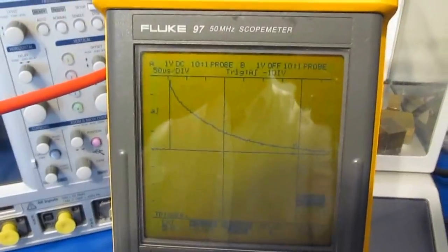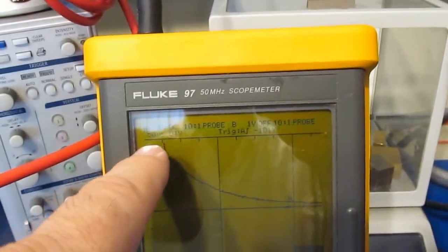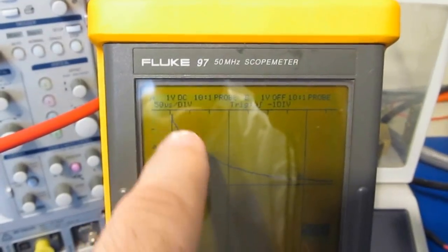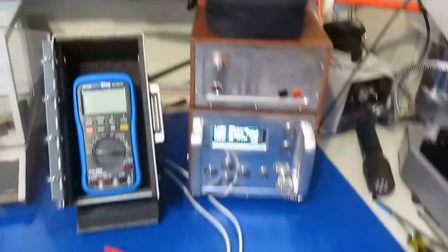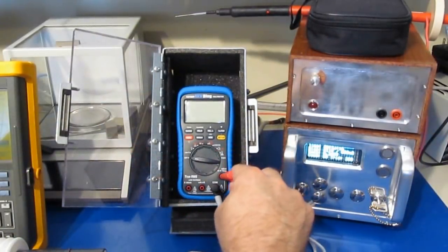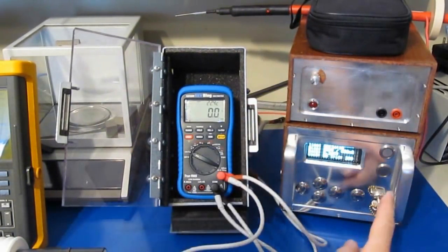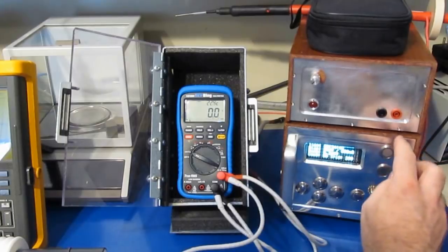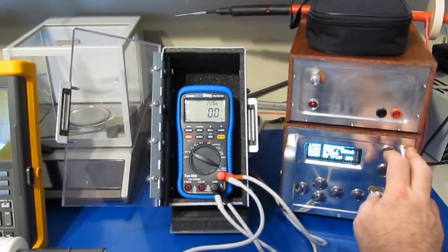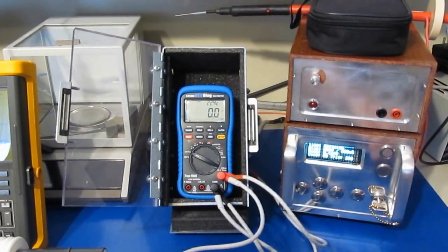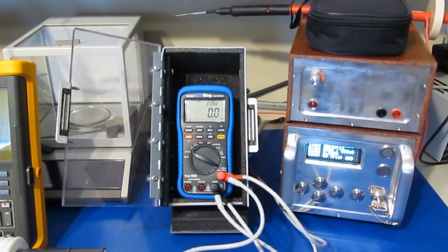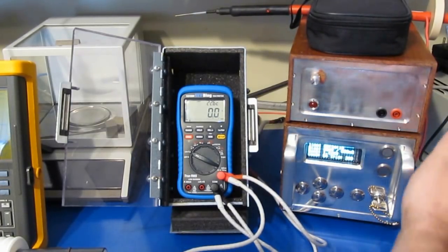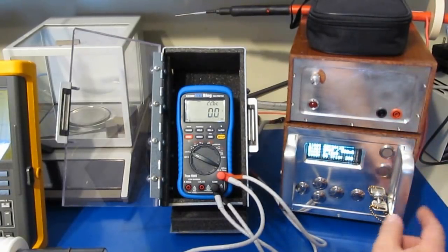Wow, the glare is just terrible. So anyway, you can see we're still at 1000 volts per division. And you can see we are now at 4 divisions up, or roughly 4000 volts. Same as before, 5 transients, positive and negative, with each mode of the meter. Again, this is a 100 microsecond full width half height with a 2 ohm source. Again, not a whole lot of energy. At most, about 20 joules is all this generator is good for.